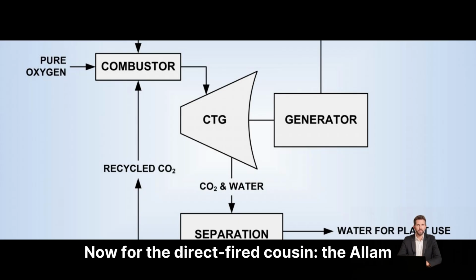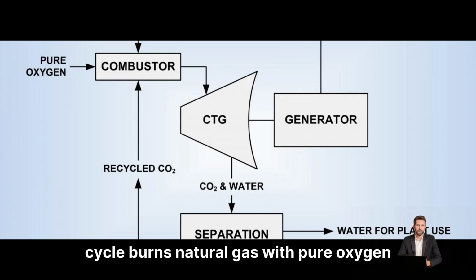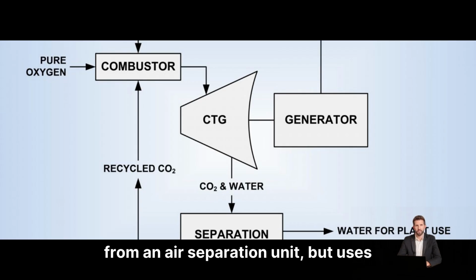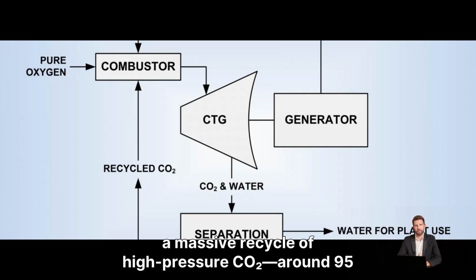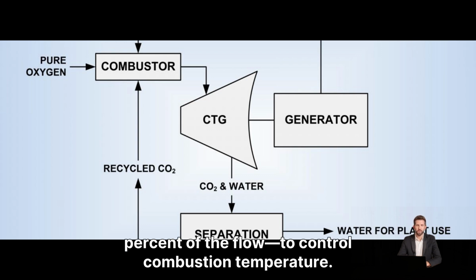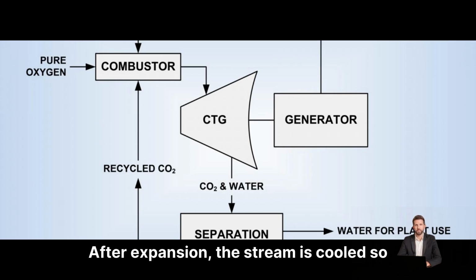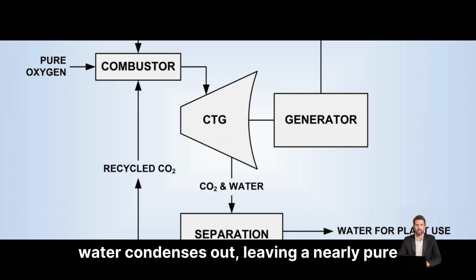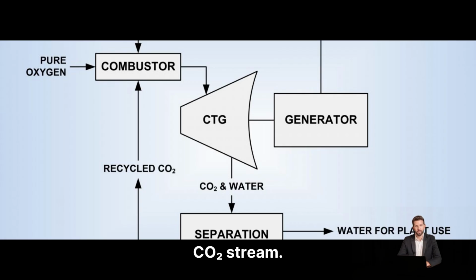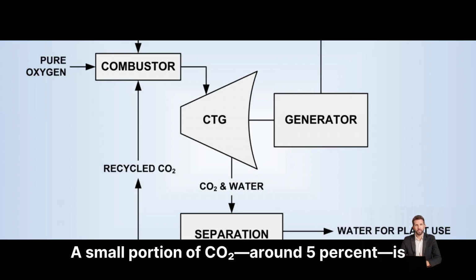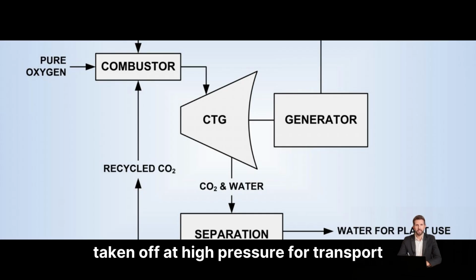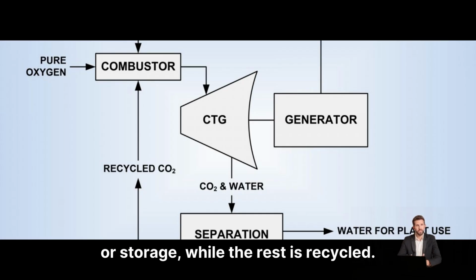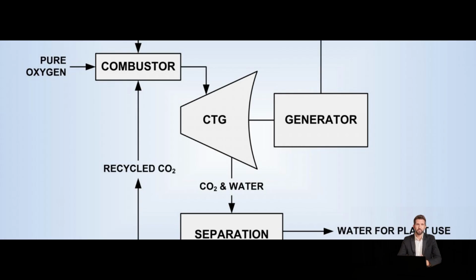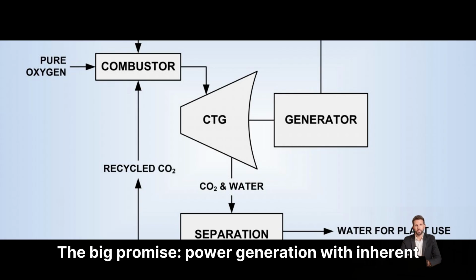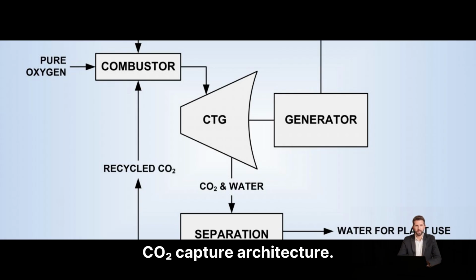Now for the direct-fired cousin. The Allam cycle burns natural gas with pure oxygen from an air separation unit, but uses a massive recycle of high-pressure CO2, around 95% of the flow, to control combustion temperature. After expansion, the stream is cooled so water condenses out, leaving a nearly pure CO2 stream. A small portion of CO2, around 5%, is taken off at high pressure for transport or storage, while the rest is recycled. The big promise: power generation with inherent CO2 capture architecture.